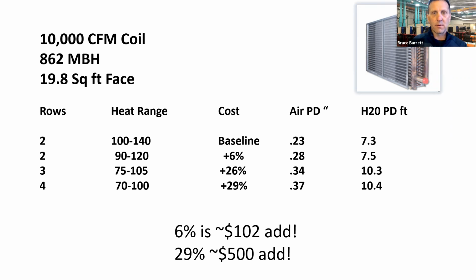You have some benefits there that you have very small coils, but you're also hurting your COP performance on the heating side. So again, I configured some coils at different temperatures and looked at the airside pressure drop and the cost added to that coil. So doing 140 degree hot water, a 2-row coil, a 0.23 pressure drop, making 120 degree hot water, it's about a 6% add and a very minimal airside pressure drop change. Now we've got to go all the way down to 105 degree hot water to add a 26% add. But even on a coil, adding 26% to a coil is not that large of a dollar add per se.